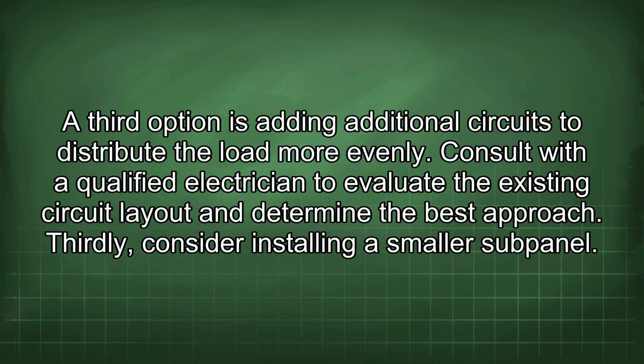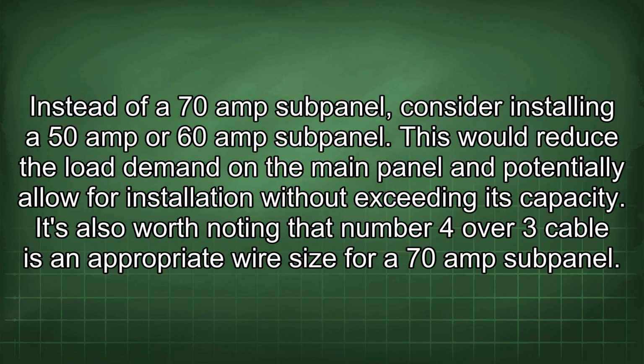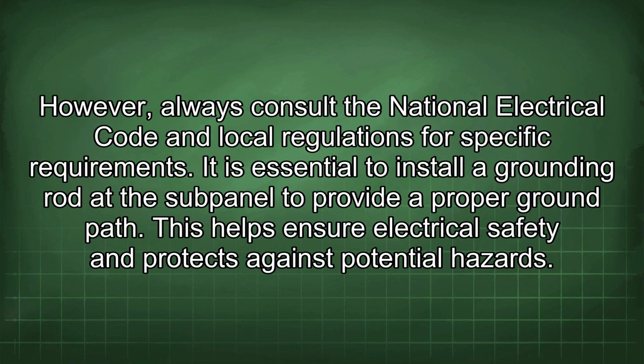Thirdly, consider installing a smaller subpanel. Instead of a 70 amp subpanel, consider installing a 50 amp or 60 amp subpanel. This would reduce the load demand on the main panel and potentially allow for installation without exceeding its capacity. It's also worth noting that number 4/3 cable is an appropriate wire size for a 70 amp subpanel. However, always consult the National Electrical Code and local regulations for specific requirements.